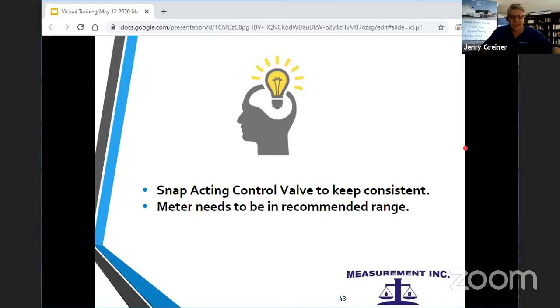You need a snap acting controller on your control valve to keep it consistent. The meter needs to be in the recommended range and the consistent flow rate. This one is right in the directive. So if you follow Directive 17 of the AER, you'll see that your snap acting control valve needs to be downstream of your meter anytime you're measuring through that meter. So it is right in the directive as well. But you quite often see them set up as throttling, especially on new systems that haven't been changed, haven't had a problem. And really, if it throttles above the minimum, it probably works pretty well. But if it drops below that minimum, it doesn't work.